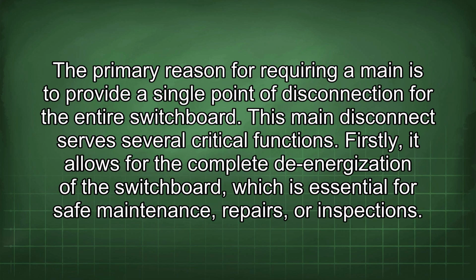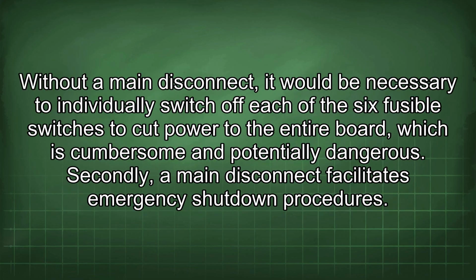The primary reason for requiring a main is to provide a single point of disconnection for the entire switchboard. This main disconnect serves several critical functions. Firstly, it allows for the complete de-energization of the switchboard, which is essential for safe maintenance, repairs, or inspections. Without a main disconnect, it would be necessary to individually switch off each of the 6 fusible switches to cut power to the entire board, which is cumbersome and potentially dangerous.